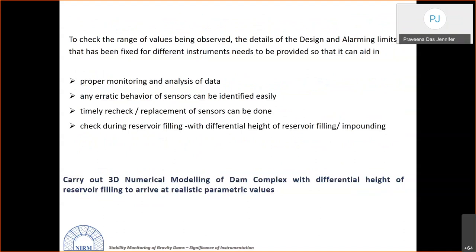Alarming limits for different instruments are fixed by the designer. These values help identify erratic sensor behavior when readings cross alarm thresholds, enabling timely sensor replacement and proper data analysis. During reservoir filling, differential heights of impounding must be checked. A 3D numerical model of the dam complex is planned to arrive at realistic parametric value assessments, since design alarm values are not yet available.